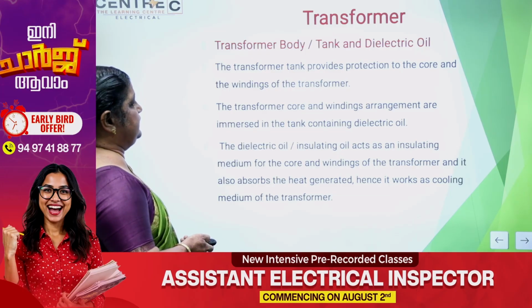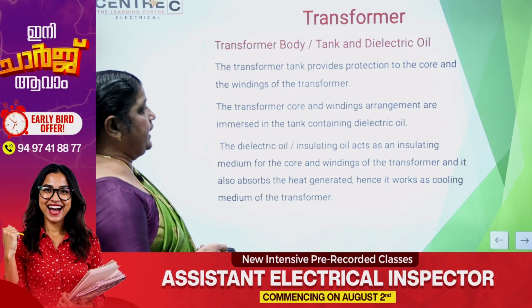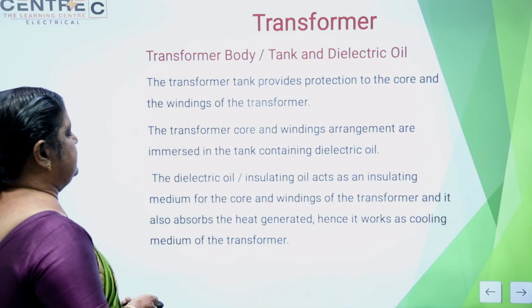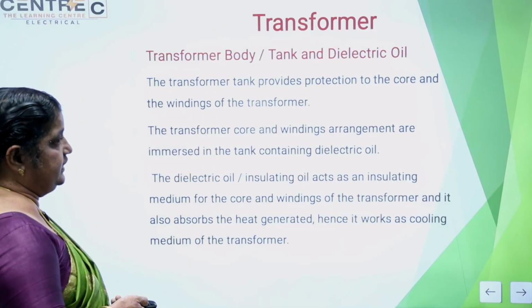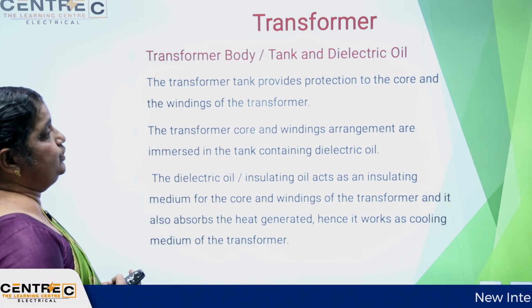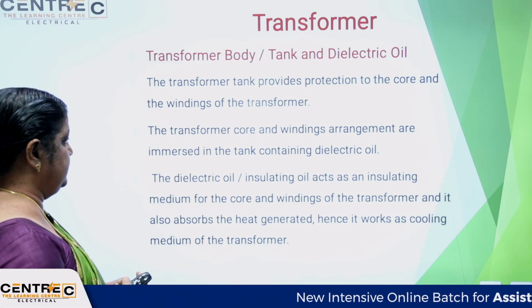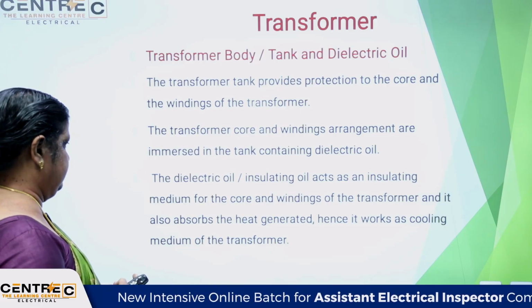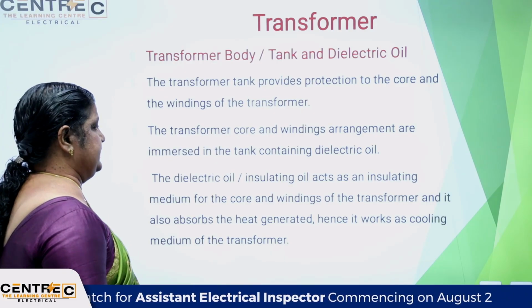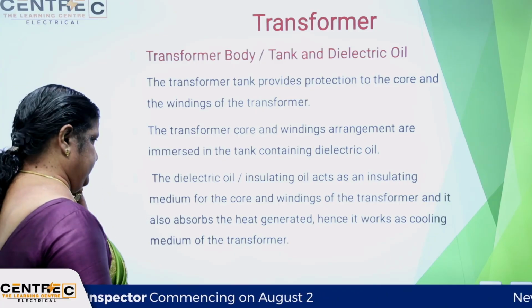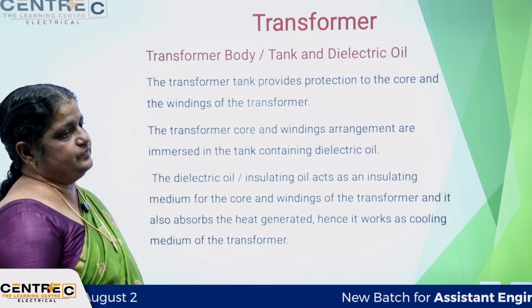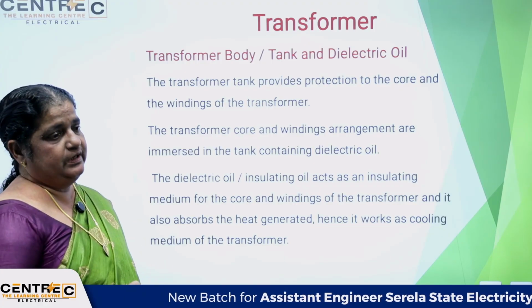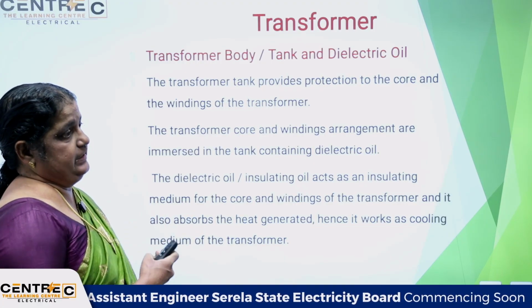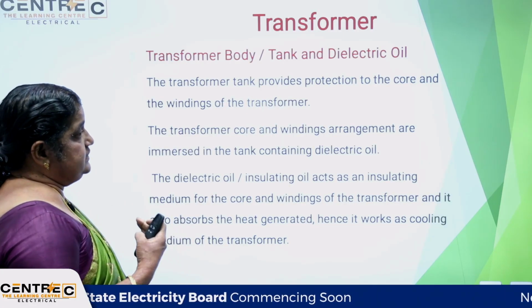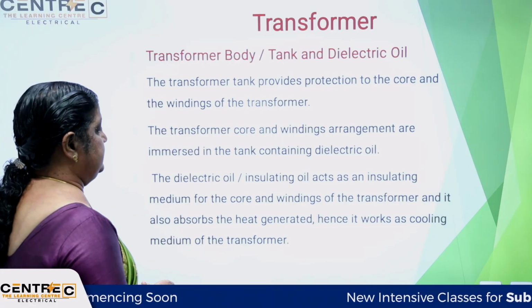Then the transformer body or tank, or dielectric oil. The transformer tank provides protection for the core and windings of the transformer. The transformer core and windings are immersed in a tank, that is a power transformer. Both winding and core are immersed in transformer oil or dielectric oil. It is used as an insulating medium for the core and winding of the transformer and absorbs the heat generated. We know that when the transformer is working, heat is produced. Due to that heat, the oil is heated, and this oil heat is removed with the help of cooling.